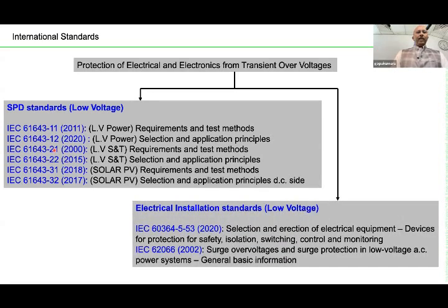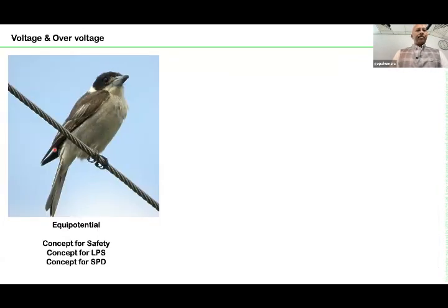Now, SPD also has to be selected and erected in an installation based on IEC 60364-553. This is the basic electrical safety standard which we spoke of last time in the hotel a few months back. 60364 is the global standard. I'm sure all of you are aware of BS 7671. So 60364 is the base standard for BS 7671. So we should also refer to these with respect to the standards.